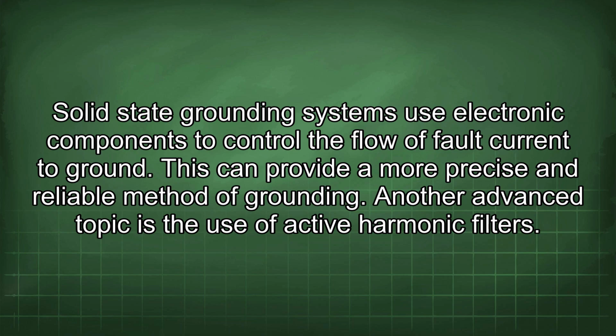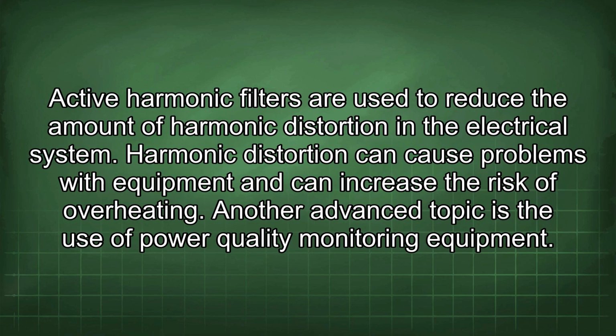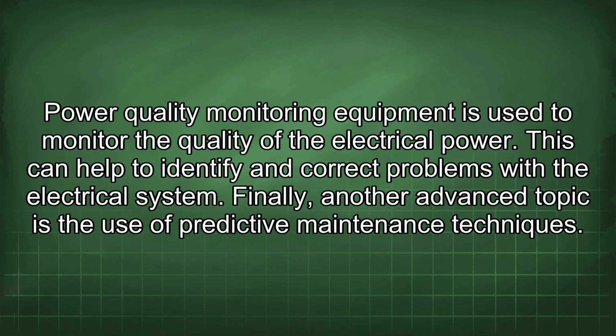Another advanced topic is the use of active harmonic filters. Active harmonic filters are used to reduce the amount of harmonic distortion in the electrical system. Harmonic distortion can cause problems with equipment and can increase the risk of overheating. Another advanced topic is the use of power quality monitoring equipment. Power quality monitoring equipment is used to monitor the quality of the electrical power. This can help to identify and correct problems with the electrical system.